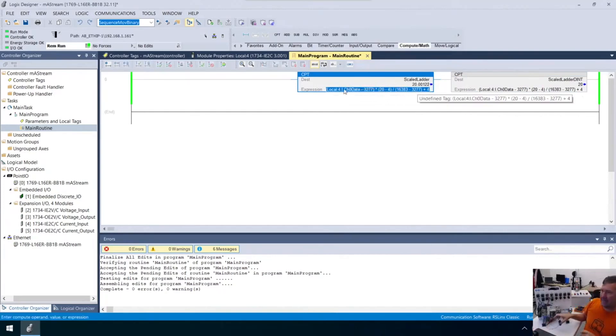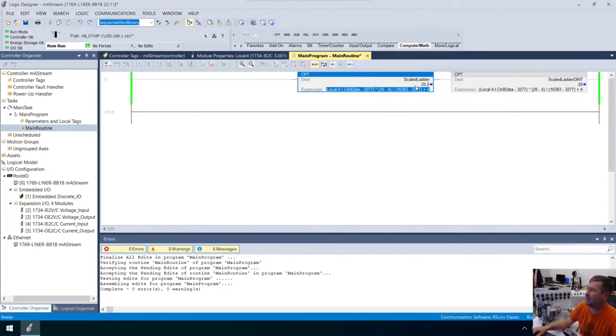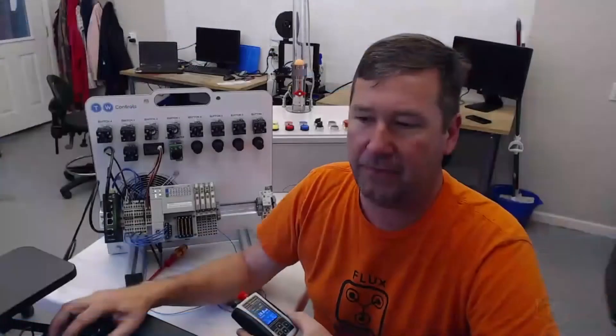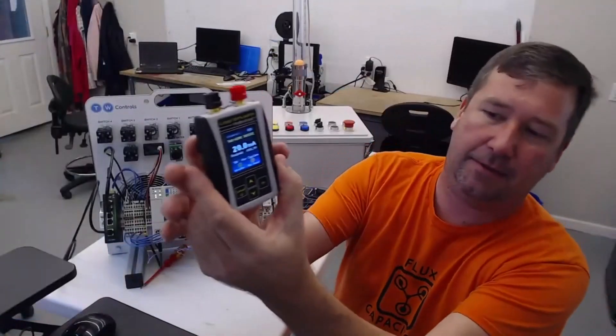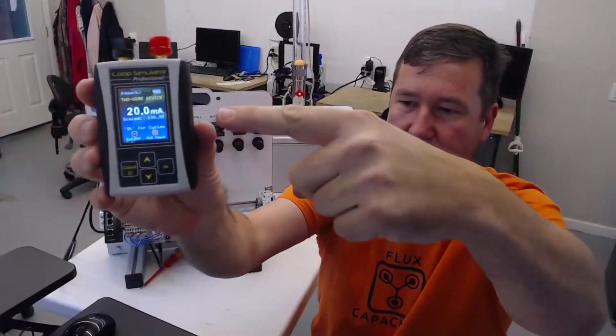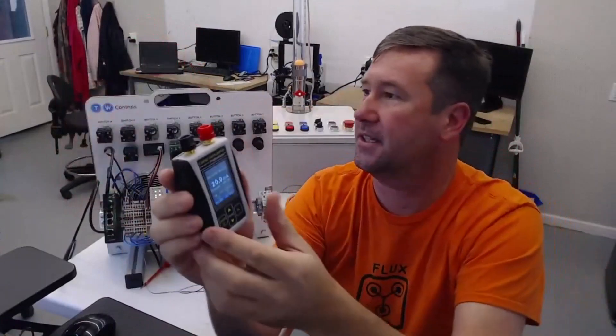So first, we're seeing a value — look at there, we got 20 milliamps. We have 20 milliamps in both of them, and if we look on our screen, yeah, we're showing 20 milliamps here. I'll put a link to the 4 to 20 milliamp lesson series in the description.